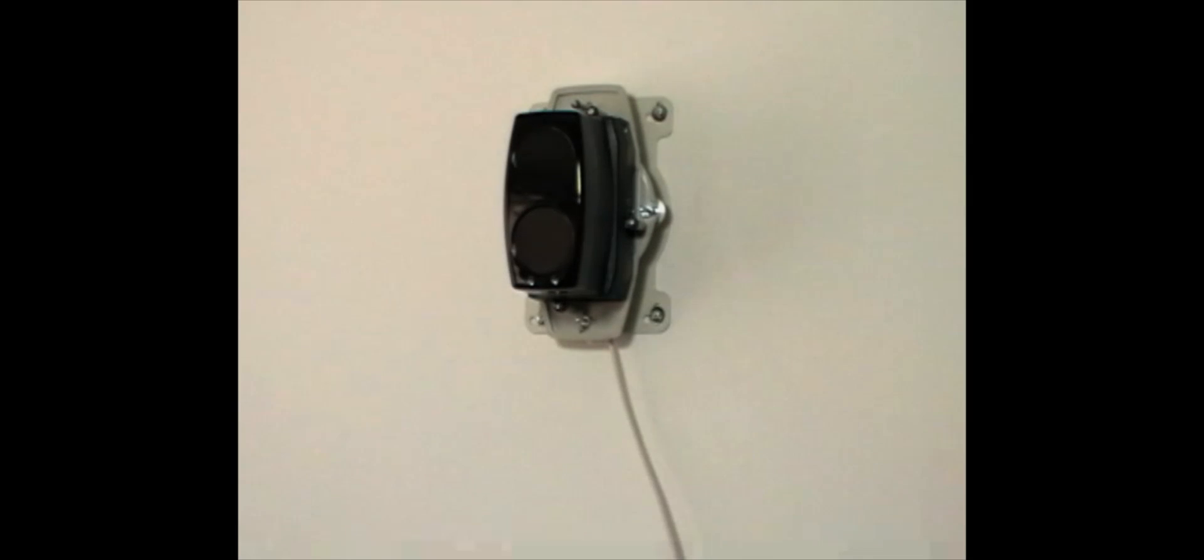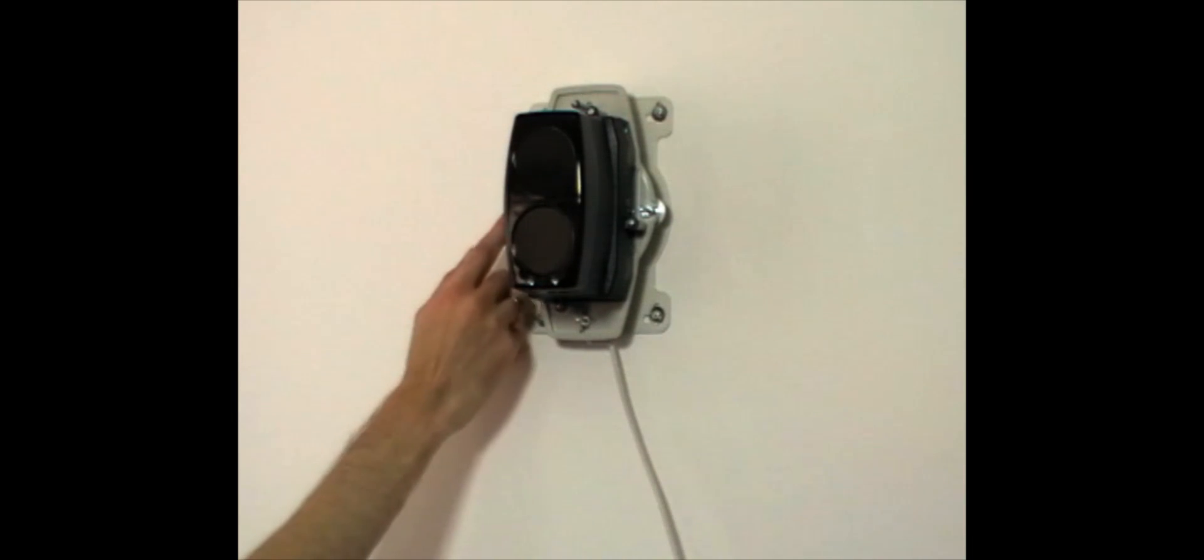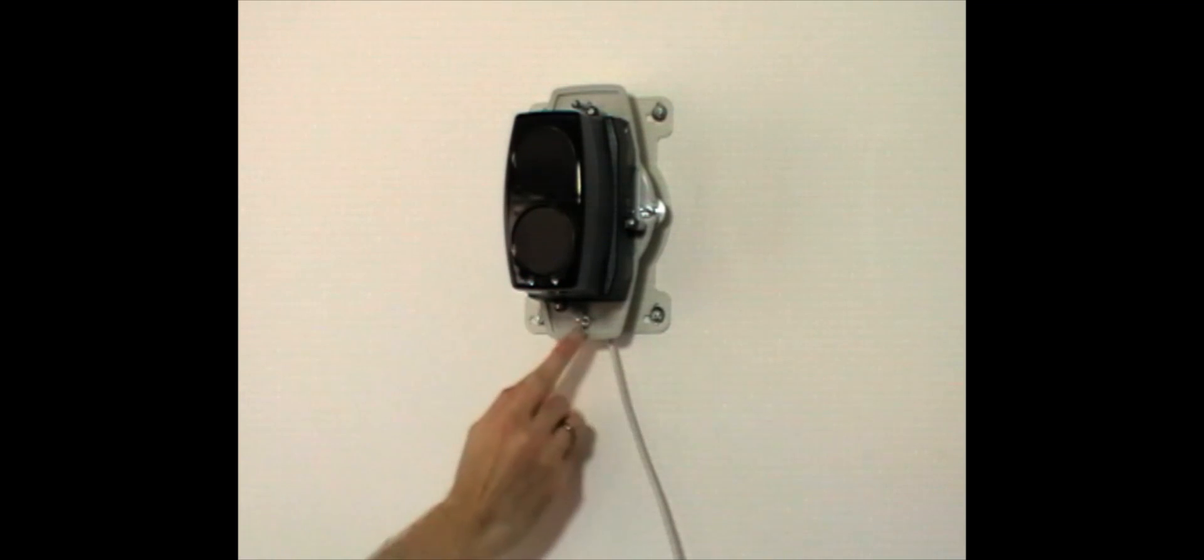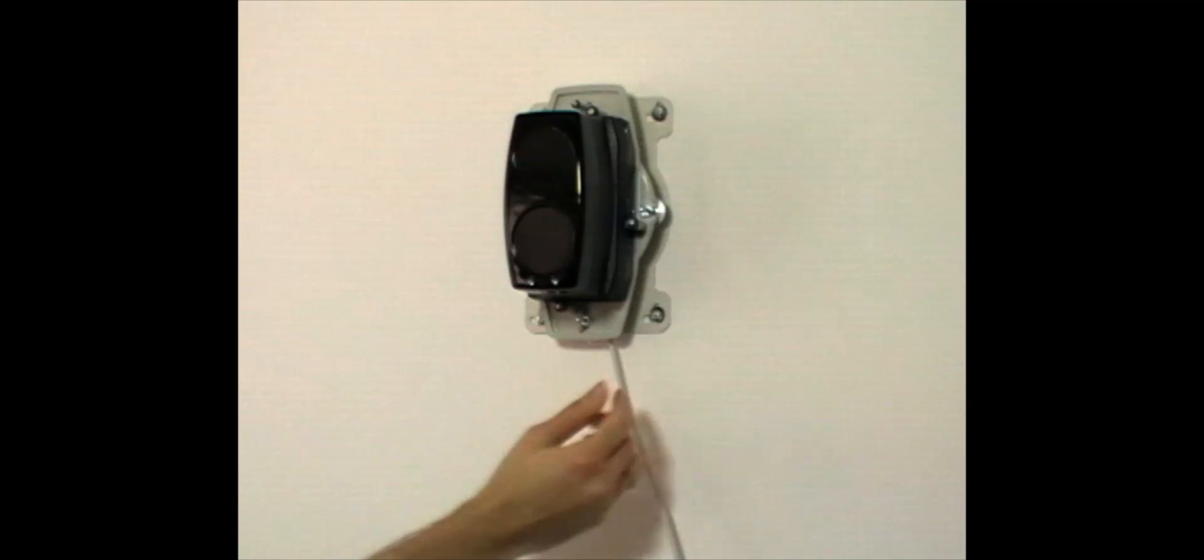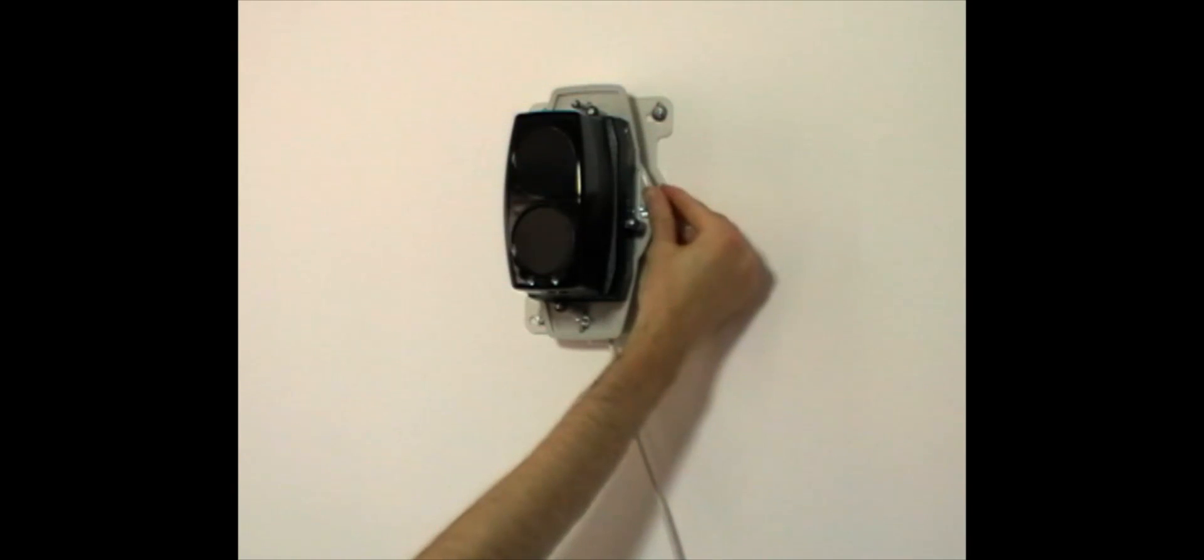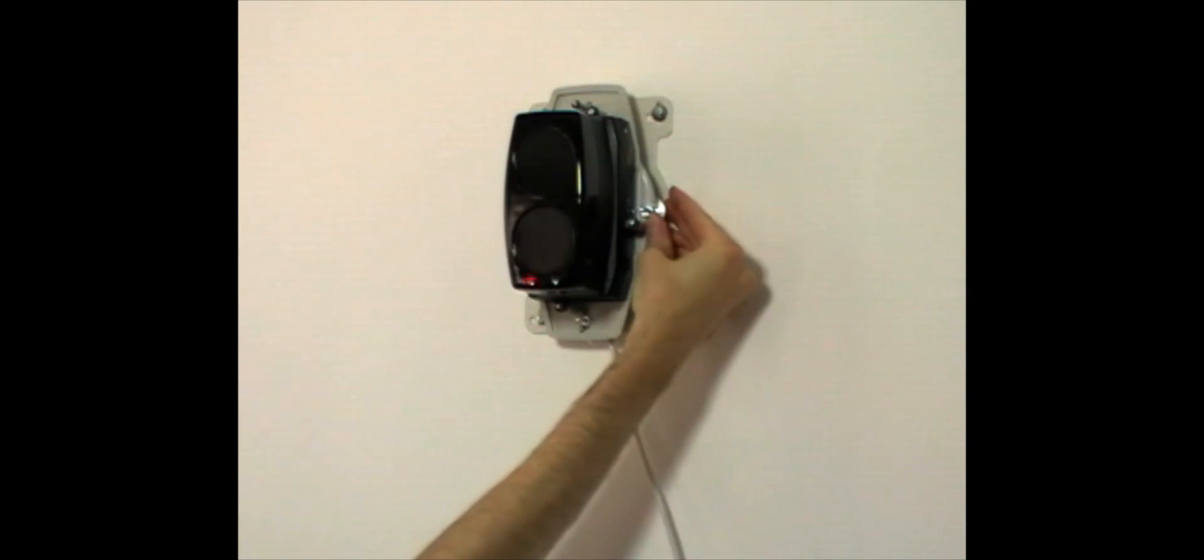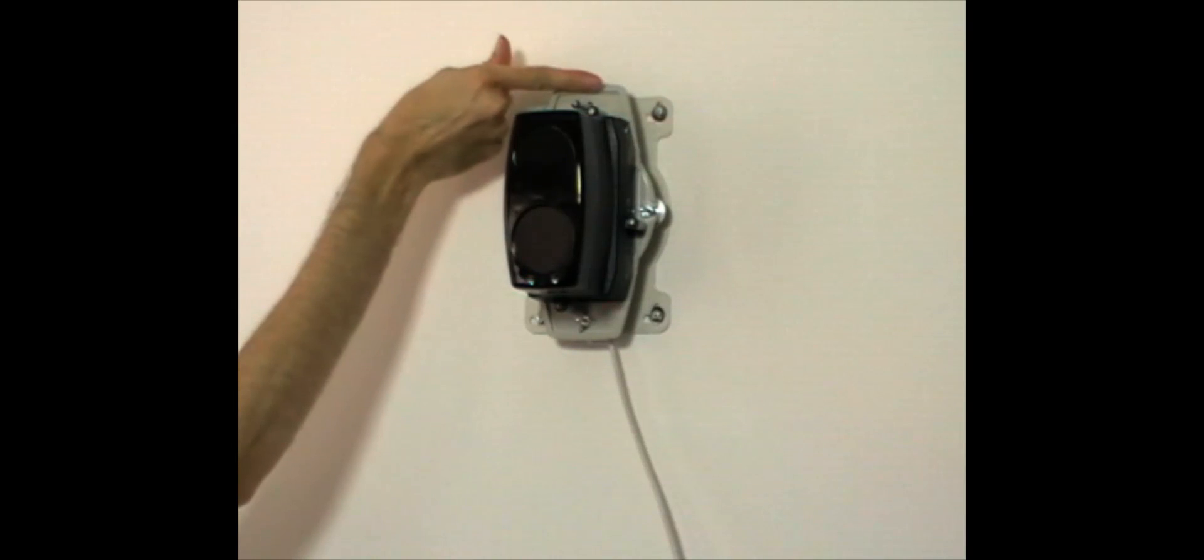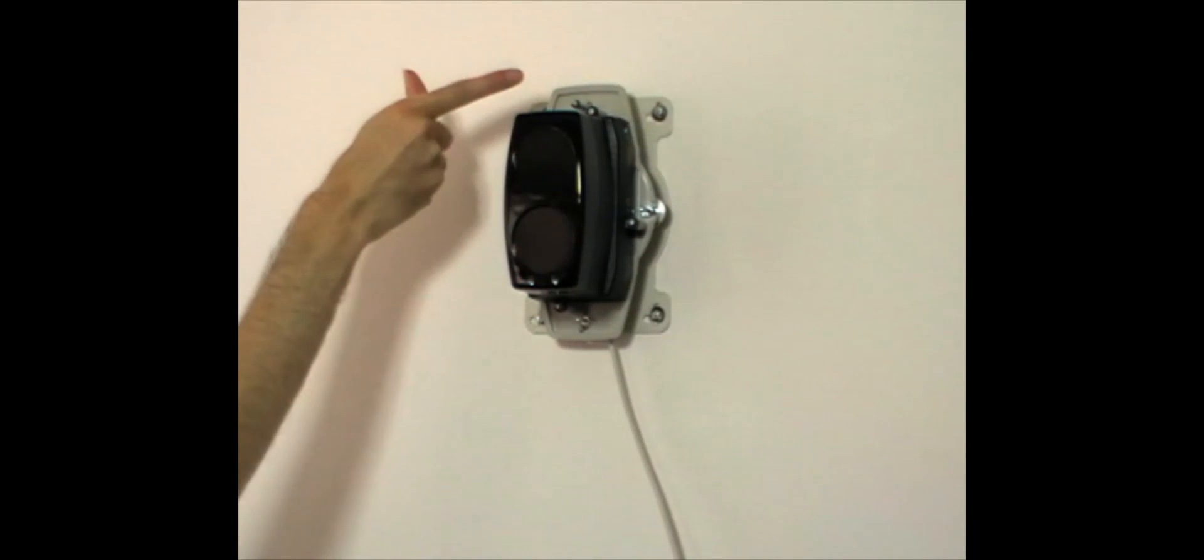You can check the beam detector is centered on the reflector just by touching each edge. Then the top and bottom of the detector head. When you touch each side of the detector head, there will be a short flash of the amber LED to indicate beam is slightly off center of reflector. And when released, no LED lights to indicate beam is centered on reflector.